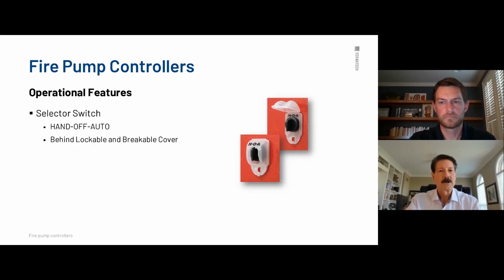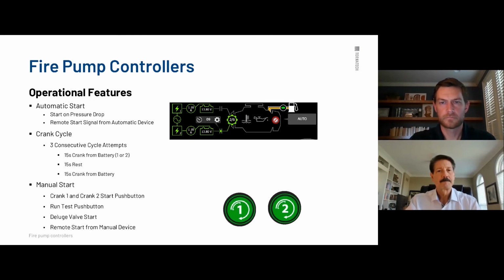I mentioned the hand-off-auto selector switch behind a breakable cover. Comes with a lock. You lock it into auto. If you ever need to break it off, you just twist this. It'll break off the ridge here, and you could put it into off. That's primarily what it is. You'll see people that still have the old little metal door with a glass cover that you got to break. But this is per UL, FM, and NFPA 20 requirements. It meets or exceeds. Keep it simple.